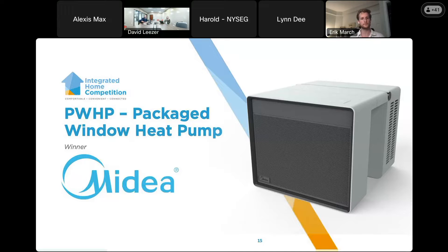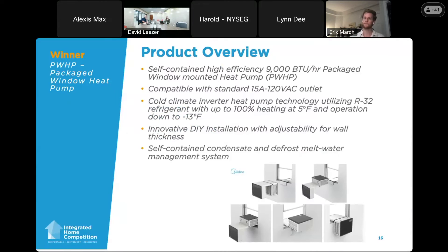This product was one of the winners from that challenge. We're currently in a demonstration phase, providing 20,000 units to help retrofit their buildings over the next several years. Essentially, it's a self-contained window heat pump. Like most window ACs that do cooling only, this is a heat pump version with 9,000 BTU heat output at 17°F. A lot of these metrics were initially dictated by the NYCHA spec from the Clean Heat for All Challenge, including the 9,000 BTUs — it's also 9,000 BTUs cooling, covering most living rooms and bedrooms.